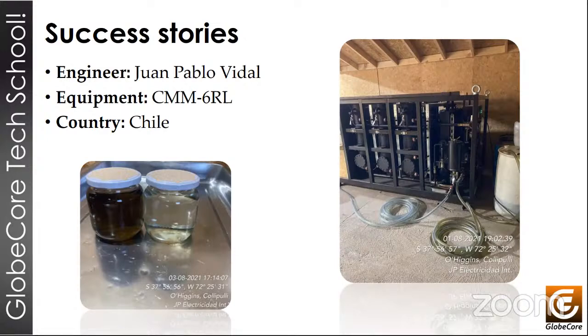This was done in Chile. This is the CMM6RL unit in Chile. On the right, you can see the photo of the plant, and on the left, you will see samples of transformer oil taken before and after regeneration. I'm pretty sure you can guess which one is which. In the left container, you see the oil before the regeneration. On the right, the clear oil is after regeneration. Even from appearance, you can see that the changes are quite significant.